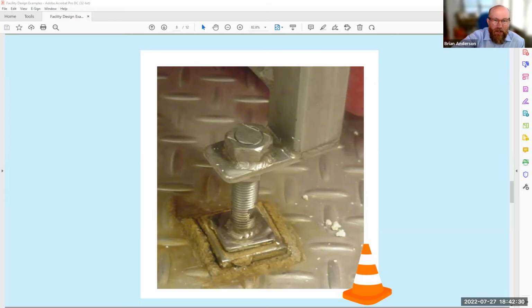The electrician that's doing a commercial kitchen one day, or a residential house, is going to have a bucket full of connectors that, in a food safety environment, are far below what's even called good. Just because they're an electrician and they're licensed doesn't mean they're carrying the correct parts you need for your facility in their van. The ability to specify that ahead of time could save you a lot of trouble.